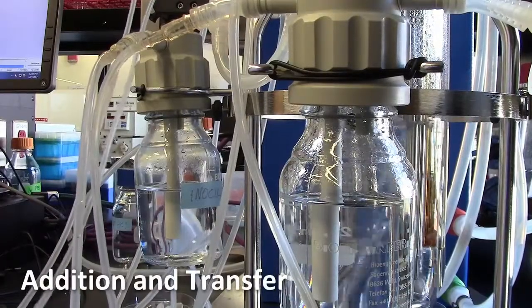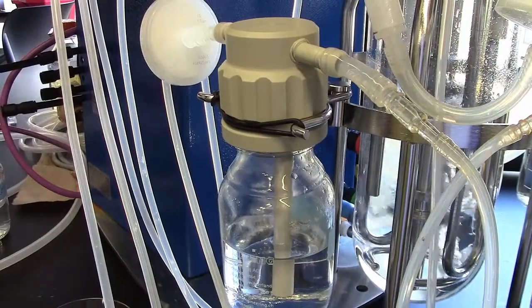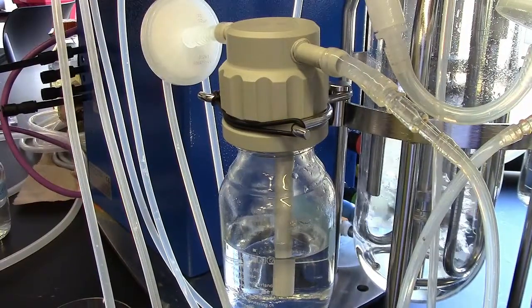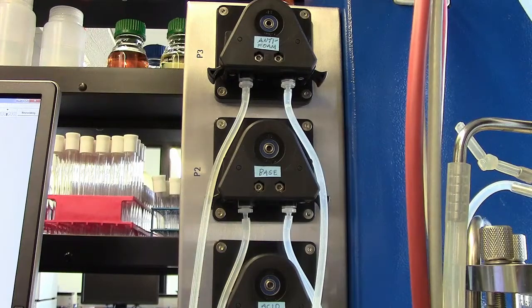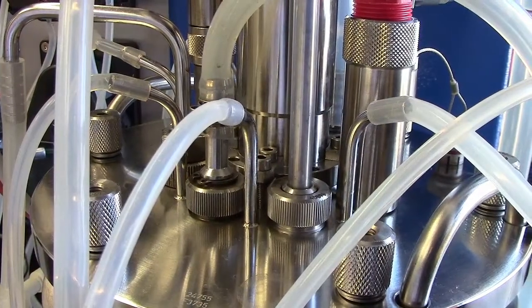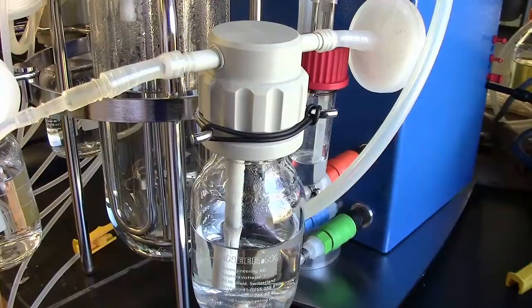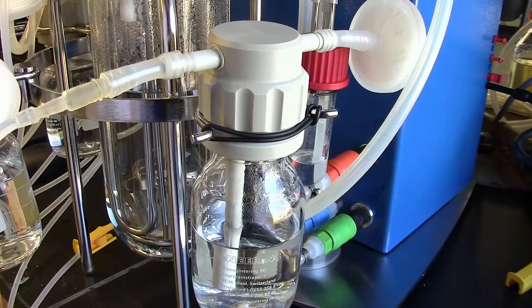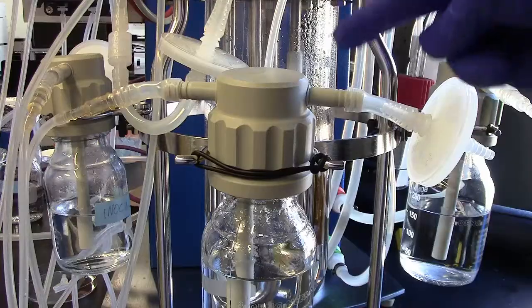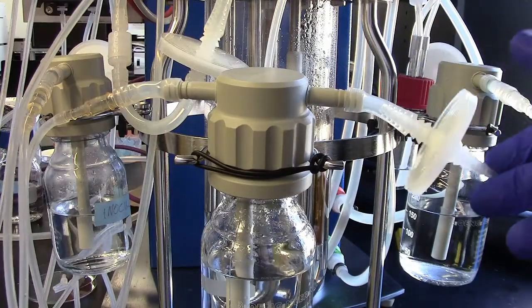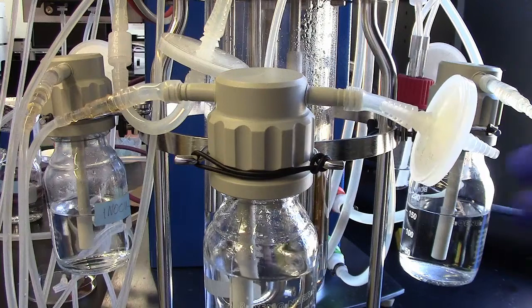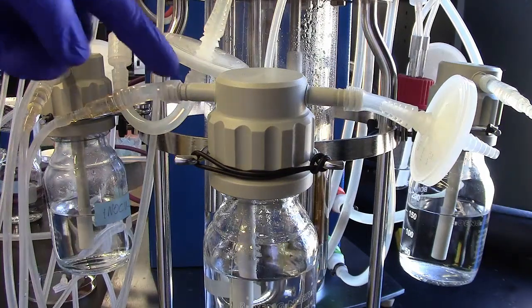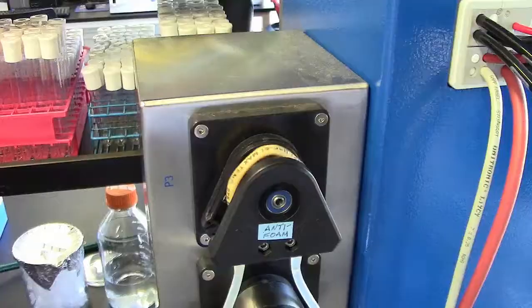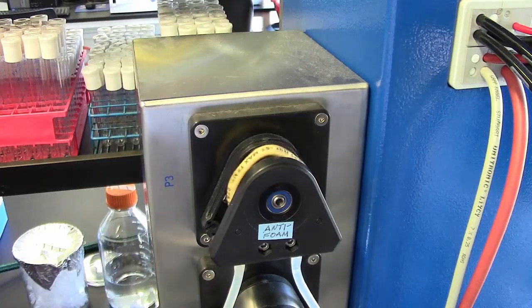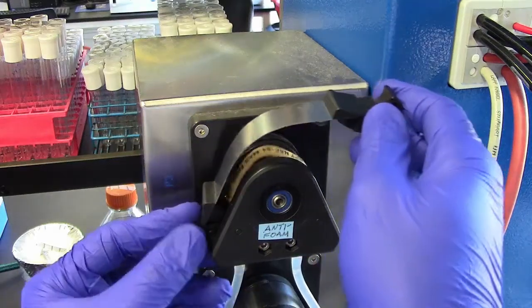Addition and transfer. The addition and transfer system consists of 3 laboratory bottles connected to peristaltic pumps, which feed into ports at the top of the fermentation vessel. The bottles are suspended from a cap that hangs on the frame surrounding the fermentation vessel and has 2 ports: an intake port fitted with a sterile filter, and an outlet port which connects the bottle to the pump and fermentation vessel. The pumps work by squeezing rollers along a section of tubing, similar to the peristaltic action of the digestive tract, hence the name.